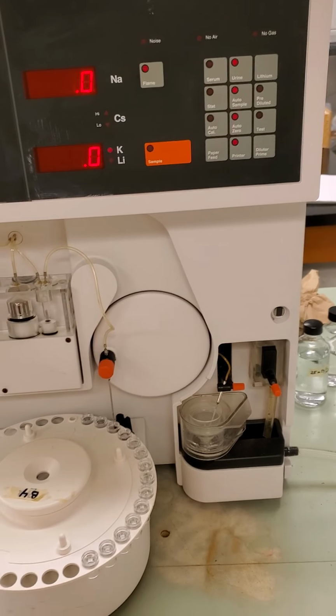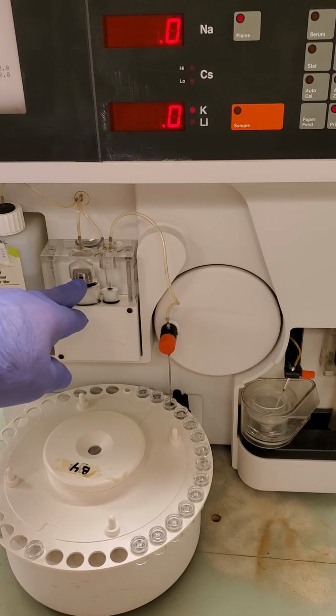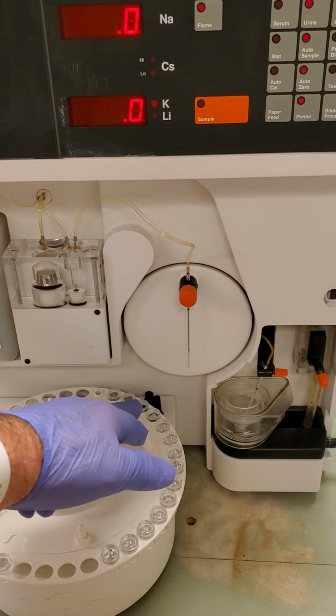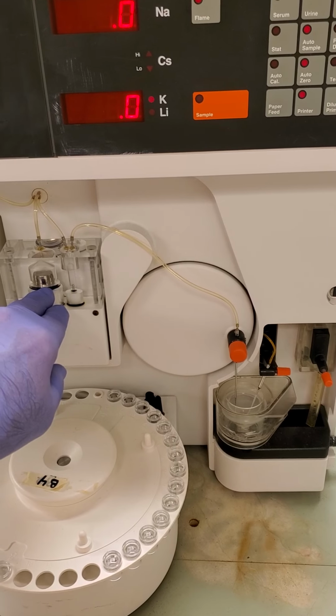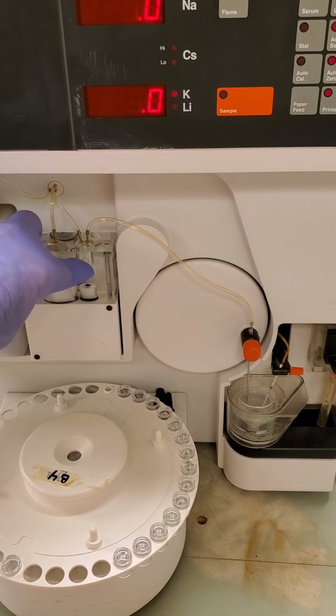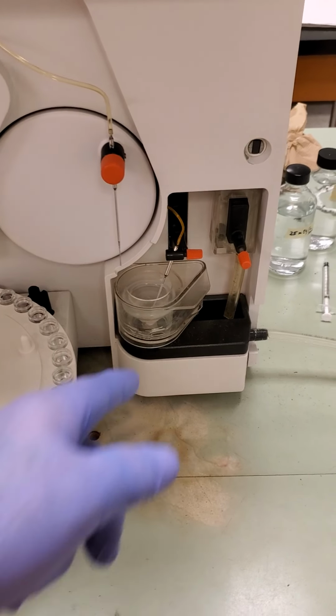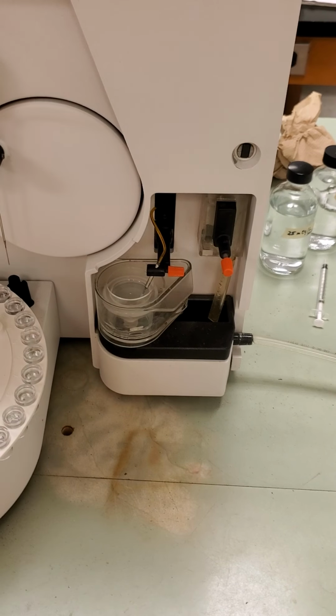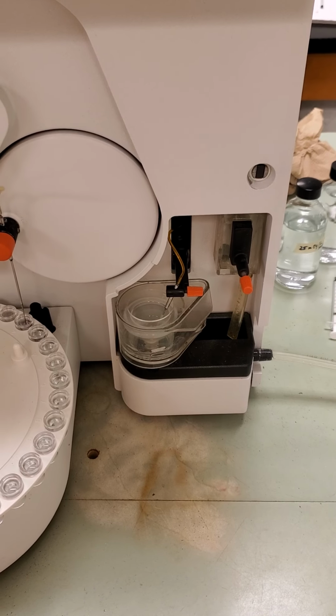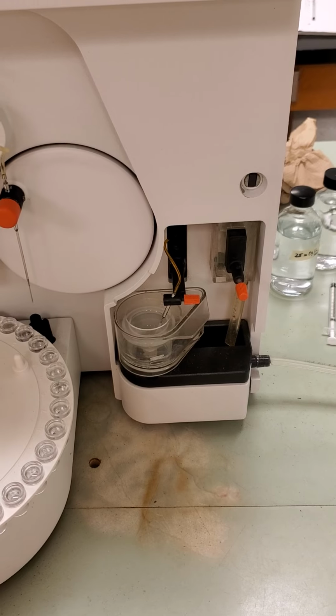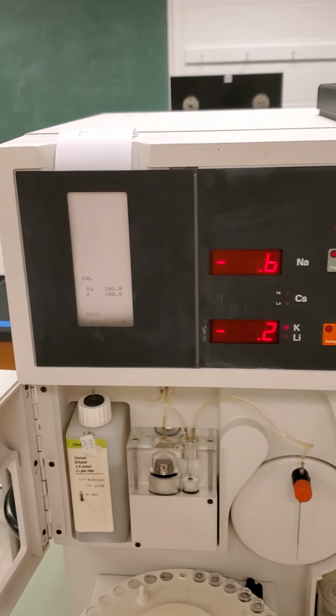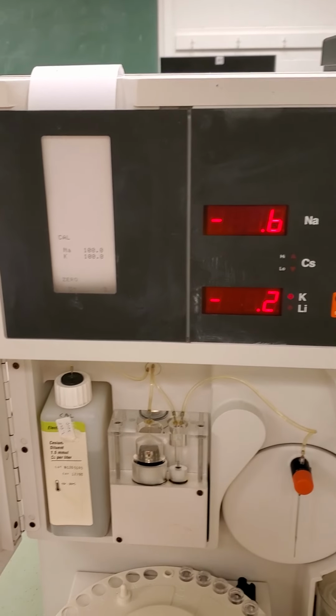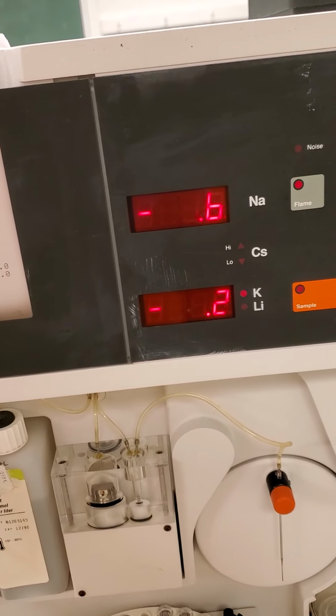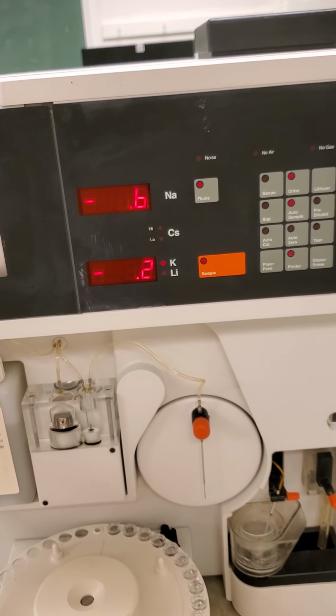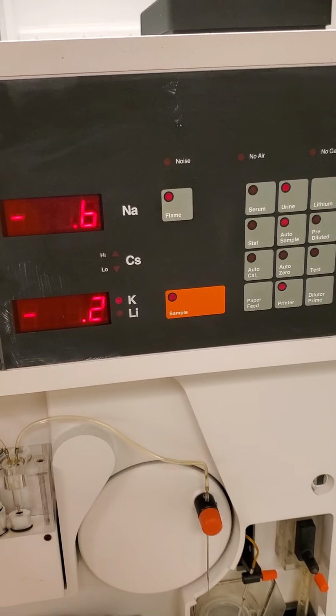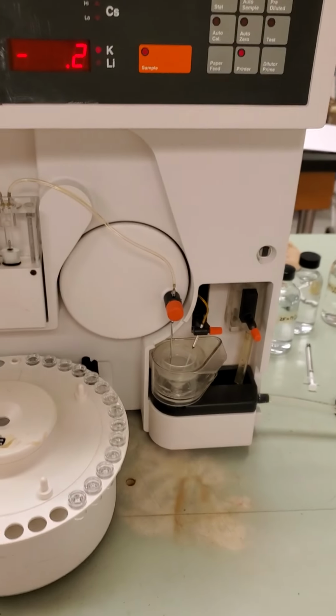So now it goes to the first sample, pulls in some of the cesium dilute right here. Then the valve switches over, and this also pulls out a sample. And so now the pistons move up, and the cesium dilute plus the sample is poured into the chamber here. It's mixed once again, and it is pulled into the burning chamber. And it'll continue, and you'll see the results. This one should be about 250. Yeah, this one that's being put in right now, it should be 250.